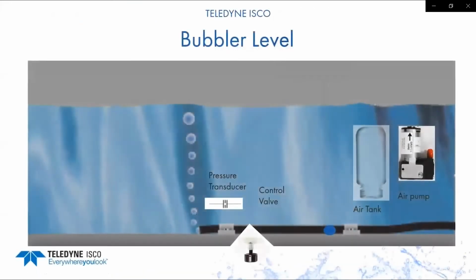Now the bubbler is shown here. It has a built-in air pump, which then pressurizes an air tank, fills it up with air. The air is then released through a control valve, and the pressure transducer reads the amount of pressure it takes to push one air bubble out. And you're going to find that most flow meters output air bubbles at 1 to 2 per second.